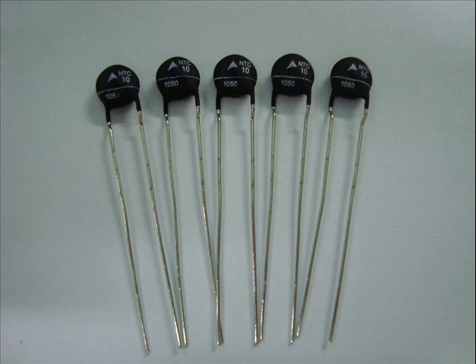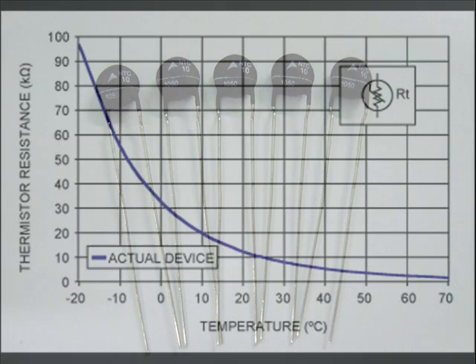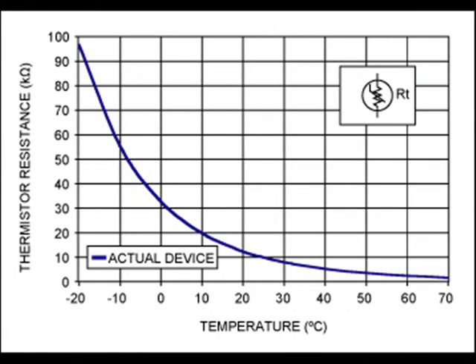The NTC, negative temperature coefficient thermistor, decreases its resistance as temperature increases. We'll be using the NTC 10K thermistor. It's called a 10K thermistor because at 75 degrees Fahrenheit, it has a resistance close to 10,000 ohms. This curve shows how the resistance of thermistor changes between minus 20 degrees centigrade and 70 degrees centigrade.